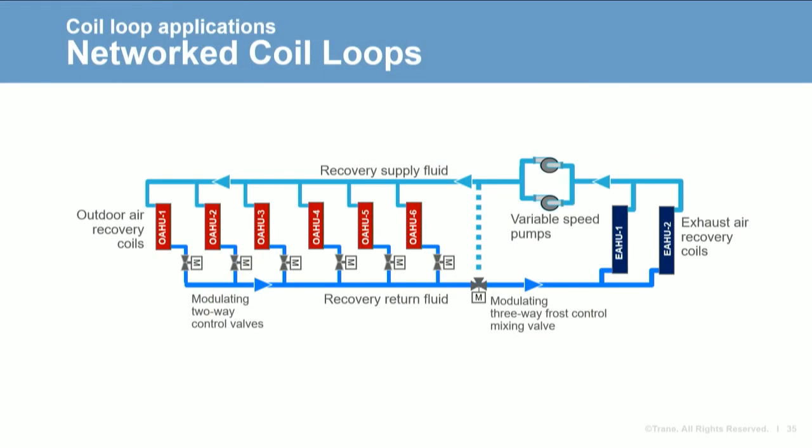Here's an example where heat is recovered from a laboratory exhaust system. Two coils are placed in two separate exhaust systems to reclaim heat, which is then transferred to six different air handlers to precondition the incoming ventilation air. There will be more piping, a larger pump with more pump power, and more glycol when there's a large distance between the coils or if multiple coils are used in a networked coil loop system.